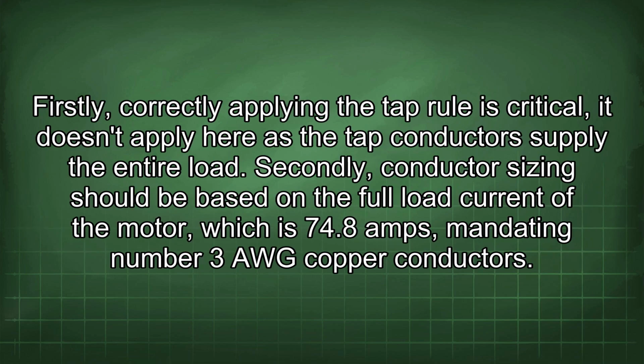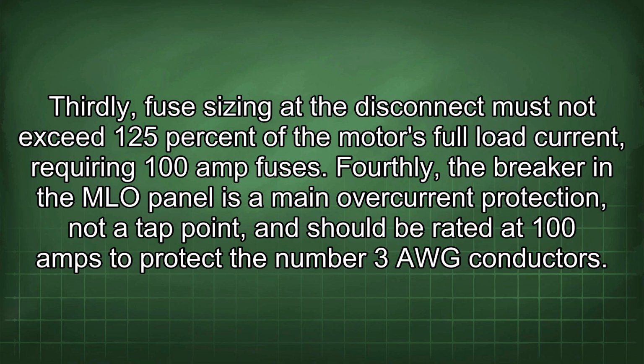Firstly, correctly applying the tap rule is critical. It doesn't apply here as the tap conductors supply the entire load. Secondly, conductor sizing should be based on the full load current of the motor, which is 74.8 amps, mandating number 3 AWG copper conductors. Thirdly, fuse sizing at the disconnect must not exceed 125% of the motor's full load current, requiring 100 amp fuses. Fourthly, the breaker in the MLO panel is a main overcurrent protection, not a tap point, and should be rated at 100 amps to protect the number 3 AWG conductors.